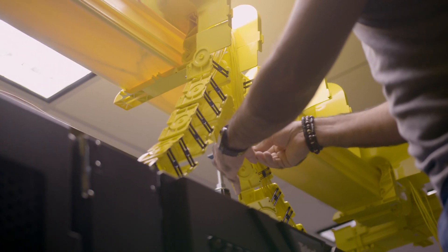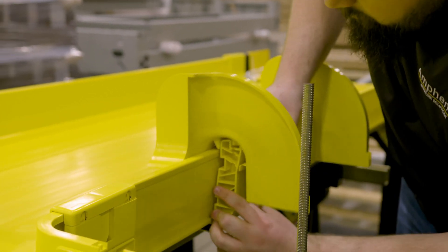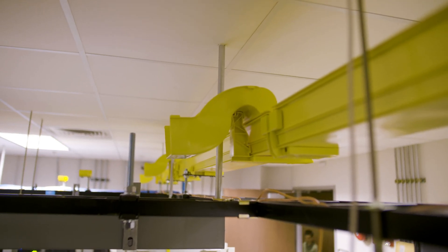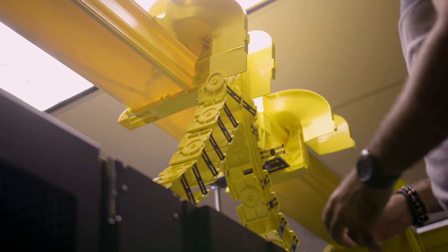The Wavetrak express off-ramp provides a modular exit that snaps onto the side of an existing 4, 6, 12, or 24 inch trough run. The off-ramp guides cable up and over the sidewall of the trough, then down into the desired bay with a 30 millimeter cable bend radius throughout the transition.